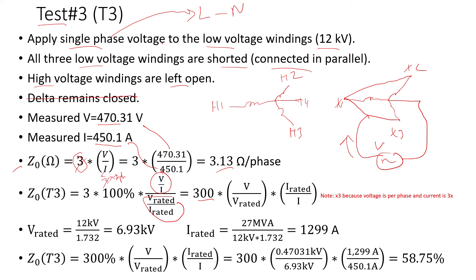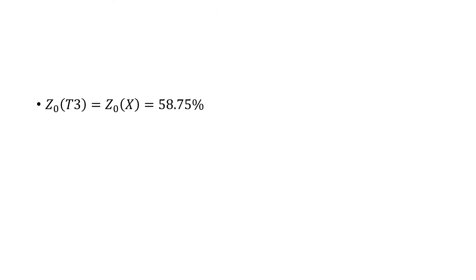Since I'm applying single-phase voltage to the 12 kV low-voltage winding, the phase voltage is 12 kV divided by √3, which gives 6.93 kV line-to-neutral. The winding is rated 27 MVA, so I calculate the rated current. Plugging in the numbers — converting volts to kV so units cancel — the amps cancel as well, and I get 58.75%. I'm noting this value because I'll need it later to build a T-model.